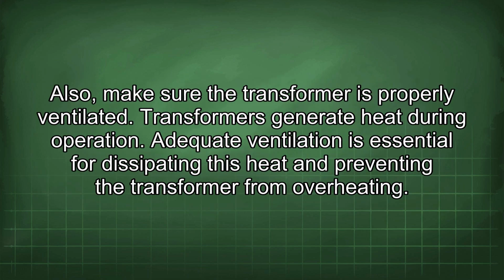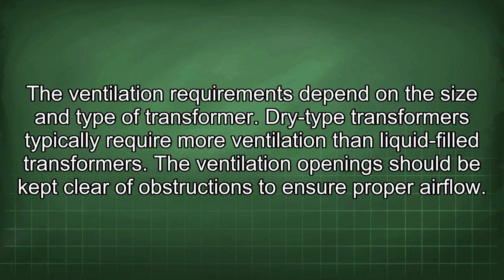Also, make sure the transformer is properly ventilated. Transformers generate heat during operation. Adequate ventilation is essential for dissipating this heat and preventing the transformer from overheating. The ventilation requirements depend on the size and type of transformer. Dry-type transformers typically require more ventilation than liquid-filled transformers. The ventilation opening should be kept clear of obstructions to ensure proper airflow.